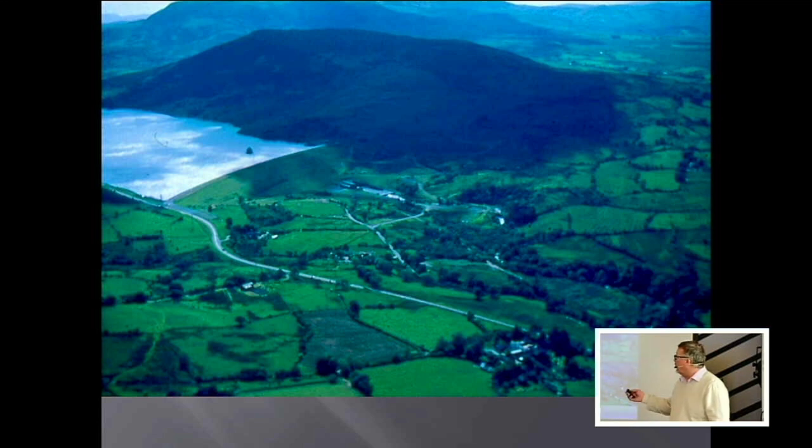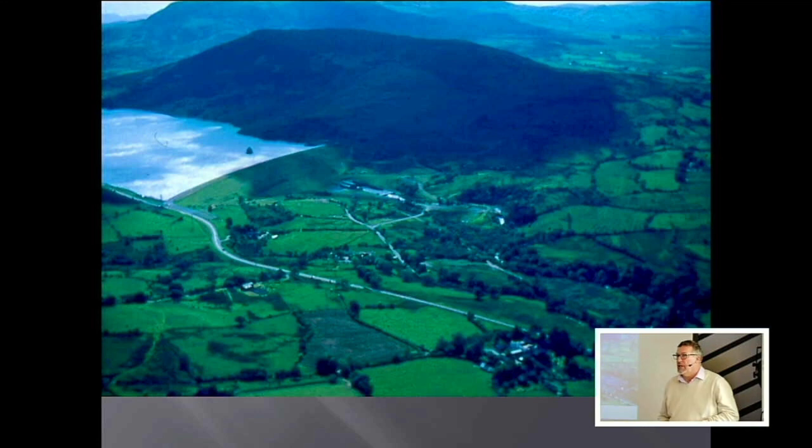There you can see the Celyn supply and the draw-off tower. Water standing in a body such as a large reservoir, sunlight can obviously affect it, ice development and that. And the water quality can change under certain depths of the water. A very hot summer, any pollution or minerals going into it, you can get a big algal growth. And this can overbalance different layers and different densities in the reservoir, and the whole thing can turn over. The water supply in the reservoir turns over due to density difference in the water and stirs up all the bottom, all the nasty bits that have sunk, the organic material, and you can get quite an obnoxious taste and problems. So water can be drawn from different depths in a tower to keep that balance right and those different temperature layers are in the reservoir.